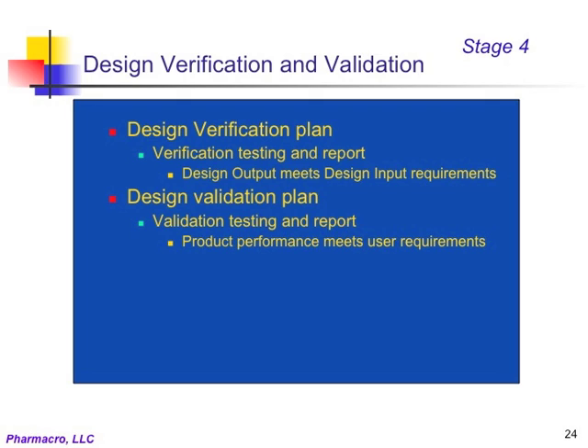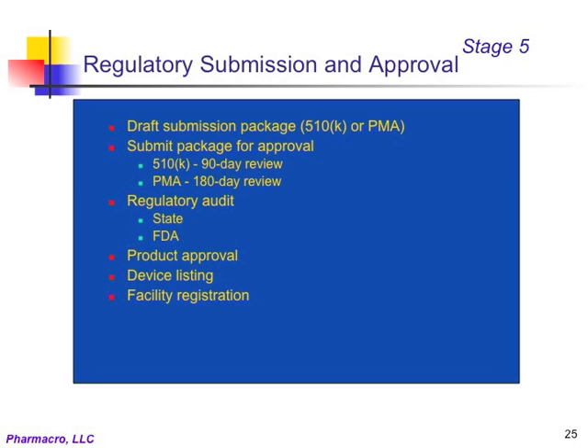Together, design verification and validation ensure that the product design meets all the requirements that were established early in the development process. After design verification and validation are completed, detailed information about the device design, the manufacturing process, and the test results are documented in a regulatory submission package. The format and content of the package are dictated by the regulatory requirements, with the 510(k) submission requiring less detail than the PMA submission. After the package of information is submitted to the FDA for review of safety and effectiveness of the device, there may be a facility audit conducted by the FDA and/or the state, depending upon the prevailing state regulations. The FDA generally chooses to conduct facility audits for devices that are high risk, particularly in the Class 3 category.